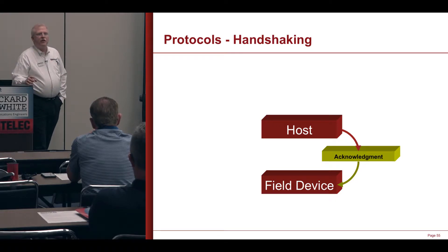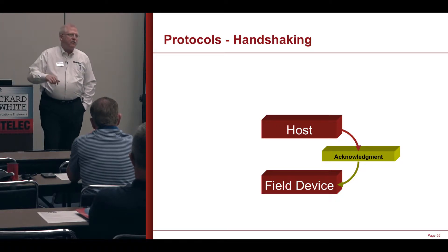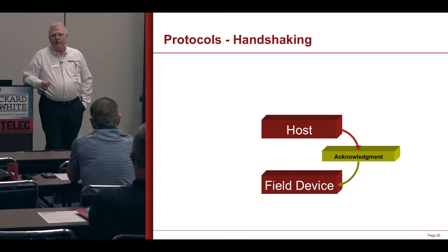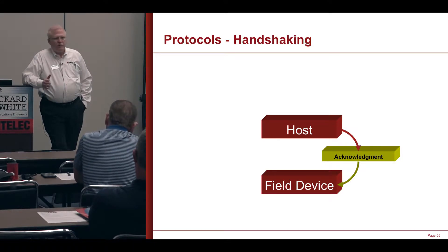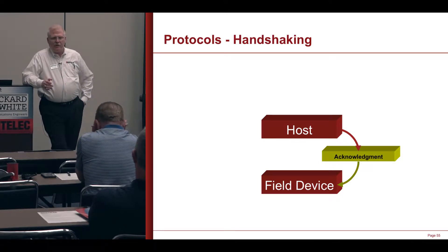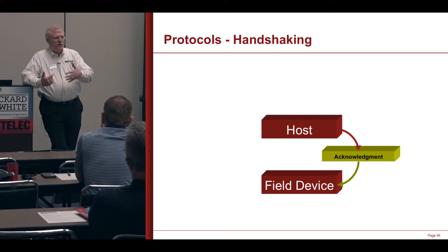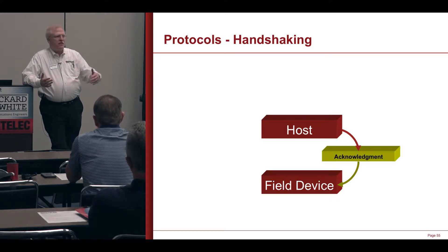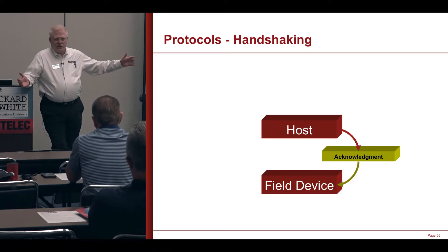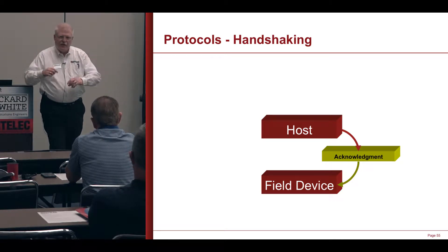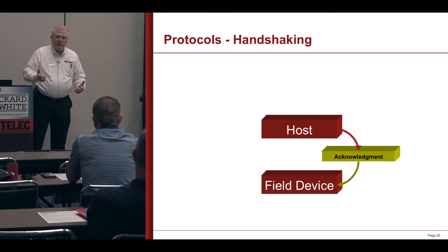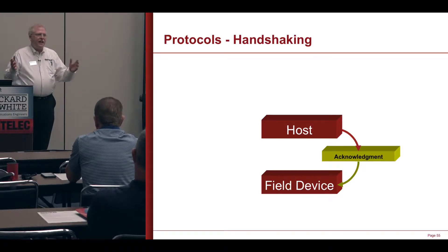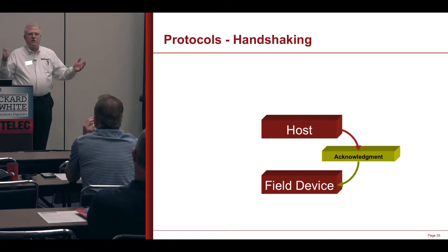There are not very many handshaking protocols left in radio telemetry. Back in the day when we were doing 300-baud radios, a handshake was important because I needed to make sure I had a key-up and the radio on the other end was talking. Otherwise it just took too long. So I put handshakes in because I got a benefit, but at 9,600-baud or 56kbit, I don't want to do that, because now it's quicker just to try and fail.